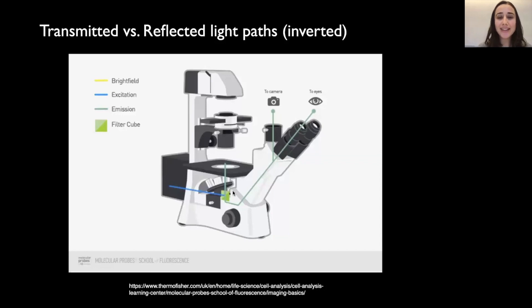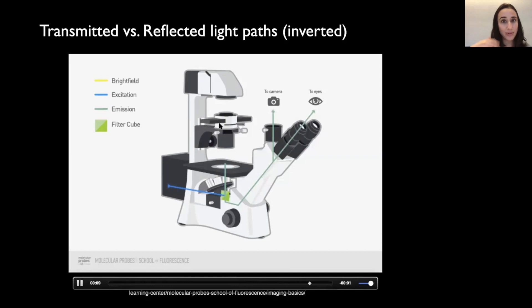Now, I would like to point out another thing that I feel that very often gets confused, which is when we look at the microscope, which components are exactly used for the fluorescence, as opposed to, for example, the bright field imaging. So for example, here again, we have the inverted microscope where we have the sample that will sit here and objectives from underneath. And therefore, our light will reflect from the dichroic to excite our sample. And then the fluorescence gets through either the camera or the ocular. Whereas the bright field uses these components over here, which is the condenser and the light source will be here. So if now we look at this animation, you see that for fluorescence, you can totally live without this part, without the condenser. And therefore, we just need the part, the light path that sits underneath.